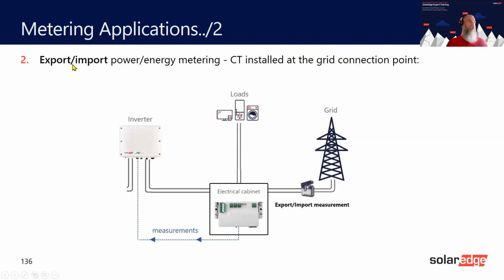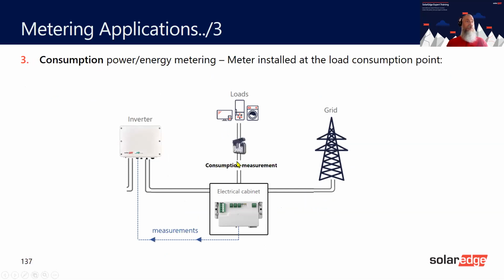If you want it for export and import, then the CT is near the grid. And if you want consumption, you then put it near the loads. If you use the meter for consumption on the dashboard, this is the value you'll get. You'll get this consumption value here. You won't be able to get individual values, unfortunately, only the group value.